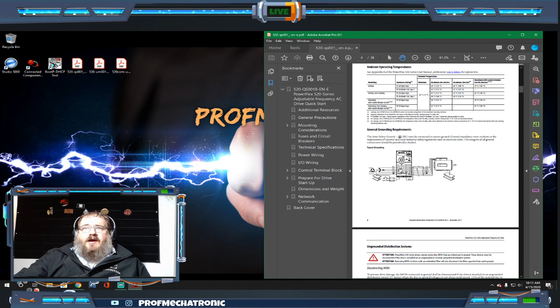Of the manuals that we have here, the first one is the QS manual, so the 520 QS manual. This is what we classify as the QuickStart manual. This QuickStart manual is extremely helpful in getting your drive going. It's only 38 pages long. Seems like a lot, but when you look at the other manuals, you'll see why it's not. This manual really covers all of the QuickStart information that you need to know: how to mount, what kind of clearances are required for all your drives, how to set up all your brakes, the grounding, the power, all that needs to be set up there. All the fuses and circuit breakers that are required for setting all this up. So all of this stuff is really covered in the manual, and typically is covered in classes as we do the wiring for those. But there are certain things that we need to talk about when it comes to actually configuring the drive.